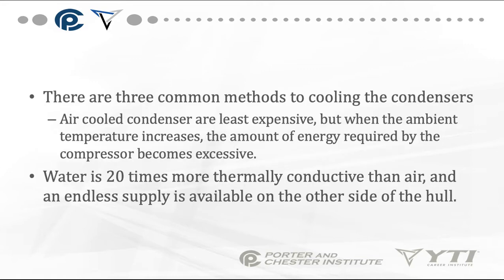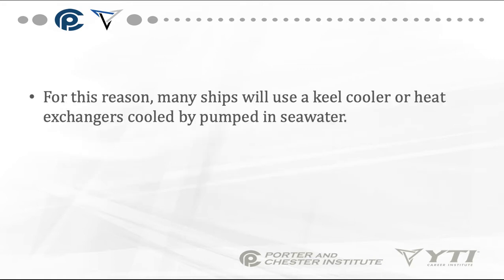There are three common methods for cooling condensers in marine refrigeration. Air-cooled condensers are the least expensive, but when ambient temperature increases, the energy required by the compressor becomes excessive. Water is 20 times more thermally conductive than air, and an endless supply is available on the other side of the hull. For this reason, many ships use a keel cooler or heat exchanger cooled by pumped-in seawater.